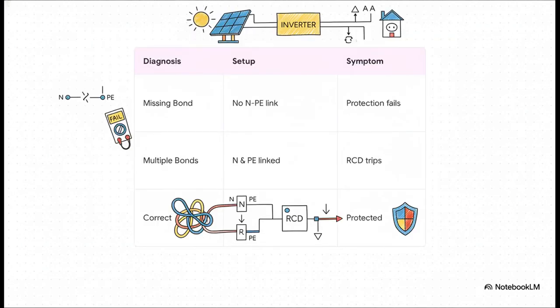It's super helpful to keep a mental diagnostic checklist handy. You can actually match your symptoms directly to wiring errors. For example, if your system seems properly earthed, but the protection fails during testing, you've probably got a missing bond. But if your RCD is constantly tripping for absolutely no apparent reason, you're going to want to hunt down those multiple bonds and get rid of them fast.